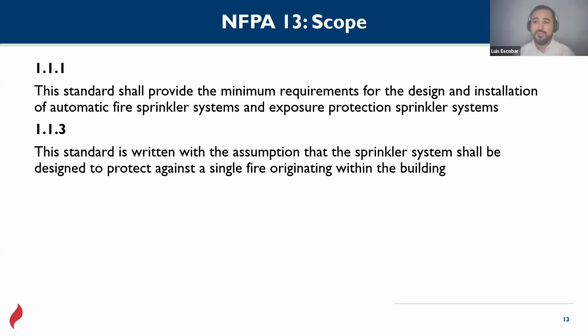NFPA 13 and any fire code will only take into account one fire at a time. If two fires occurred in totally different areas in the same building, the sprinkler system most likely is not going to work, because that's going to be provoked. Somebody set the fire, somebody initiated the fire in two different places, and that's not something that NFPA covers because a fire is basically an accident, something that happened. Probabilities are very low. So keyword, single fire originating within the building. Fire sprinkler systems are not designed to extinguish two different fires located in two different areas of the building.